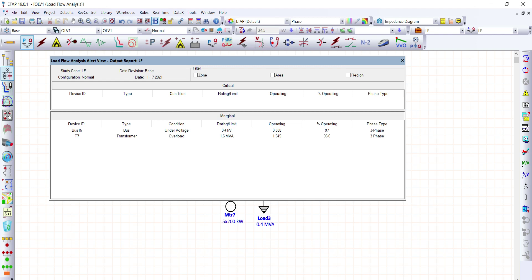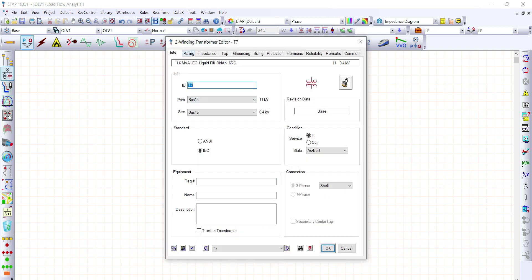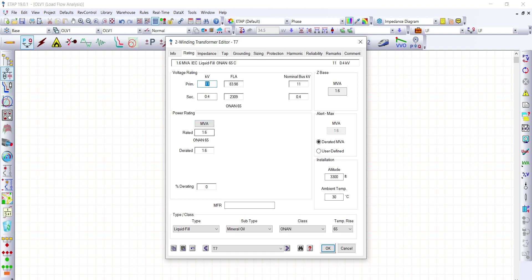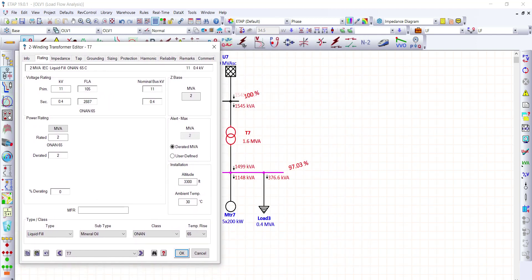To resolve the transformer overloading issue, let's increase the transformer size. Double-click the transformer, go to Rating, and change it from 1.6 MVA to 2 MVA. After re-running load flow, the 400-volt bus is now at 97.03% of nominal voltage.